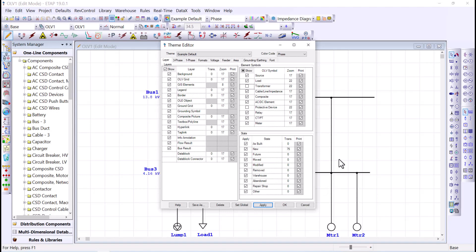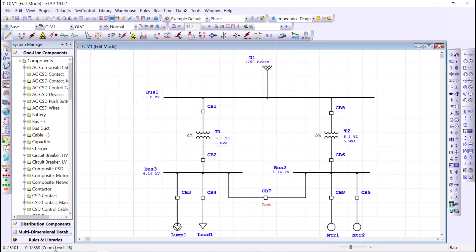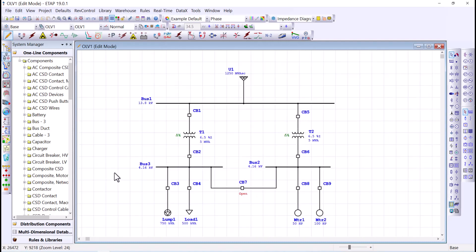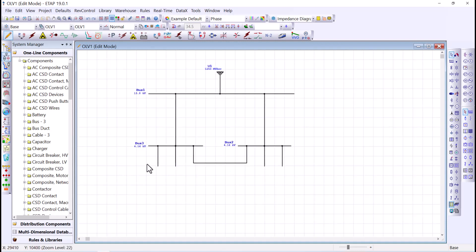I can show or hide components at a specific zoom level. If I want to declutter at zoom level 23 instead of waiting until 17, I can set that up so that below 23, the one-line diagram is decluttered while still having enough zoom level to read the buses and interconnections. That's how you use the theme manager to declutter your one-line diagram.